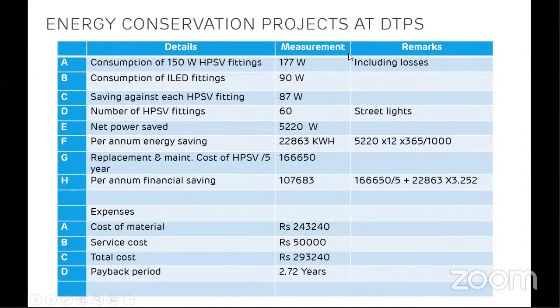Here we have given the detailed calculation. 150 watt HPSV fittings: we have measured, including the losses, the power consumed was 177 watts. Replacing it with LED, it came to only 90 watts. Saving against each HPSV, which is a high pressure sodium vapor lamp, was 87 watts.